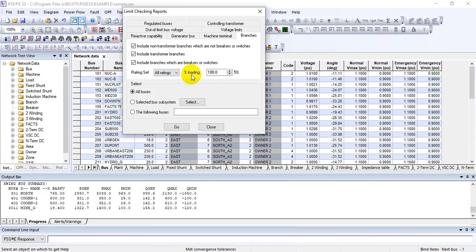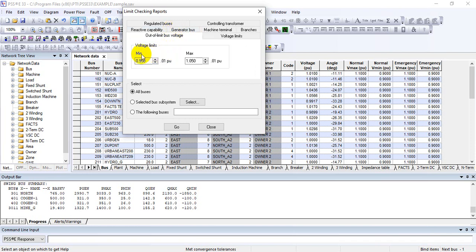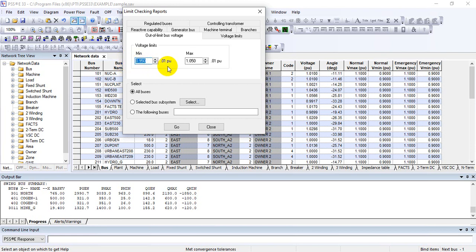We will look at each report one by one. The next important thing is the generator buses — you can see the machine summary of your online plants using this report as well. Let's start with the first report: the Out-of-Limit Bus Voltage Report. You need to give the minimum and maximum voltage limits. Under N-0 condition the limit is plus or minus five percent, and under N-1 it is plus or minus ten percent. Since we are using the steady state normal case without any contingency, let's keep the default setting of plus or minus five percent.